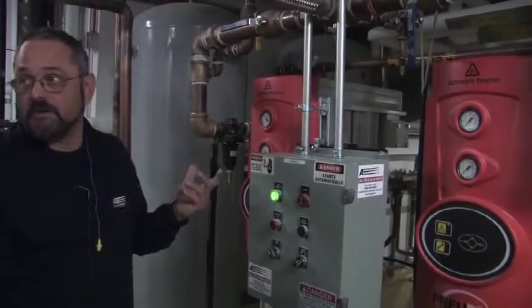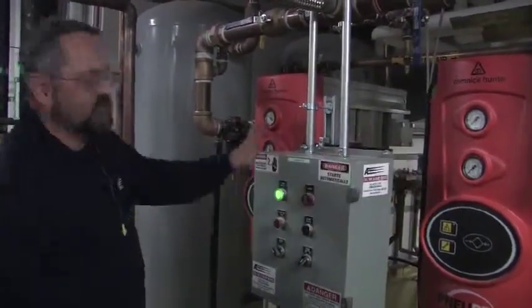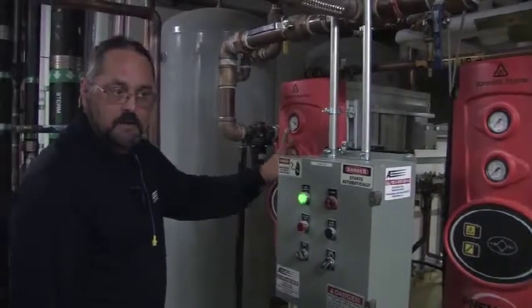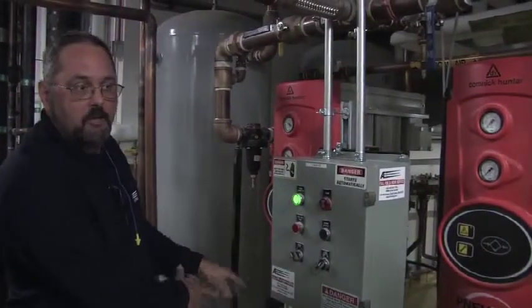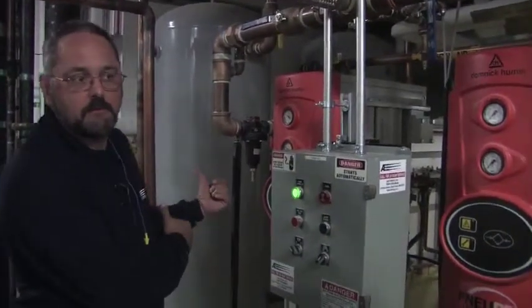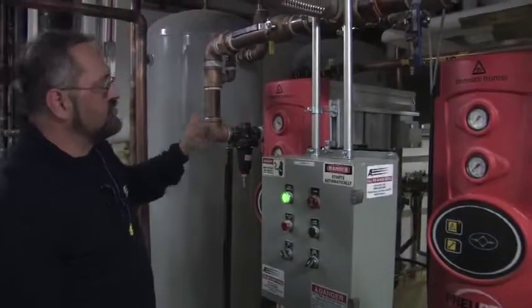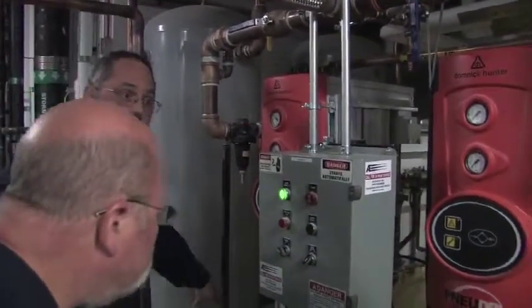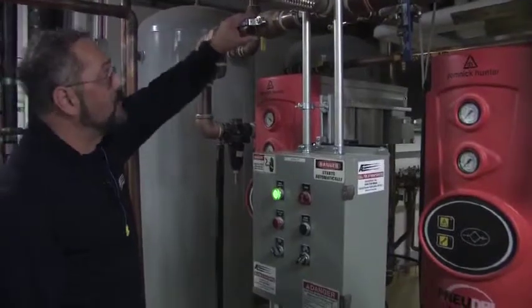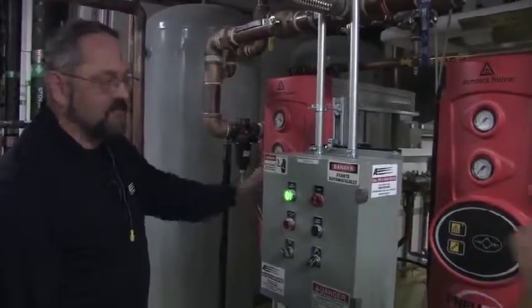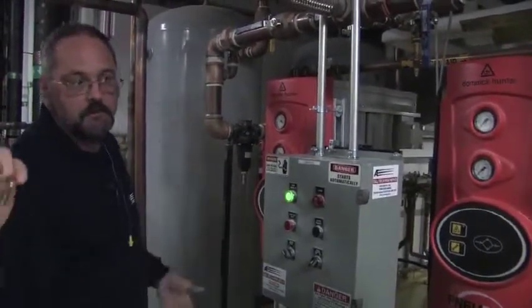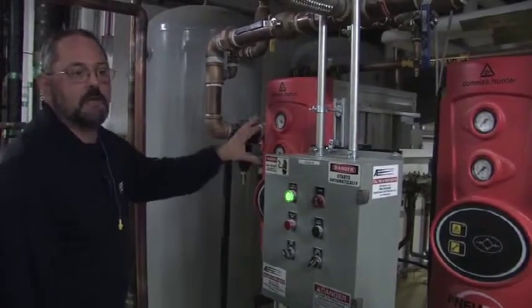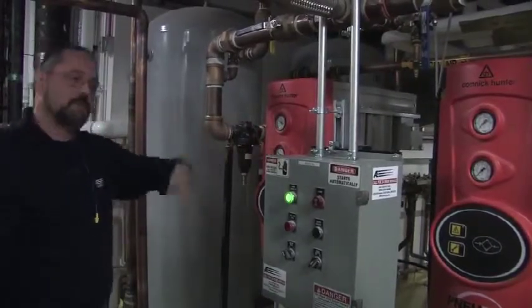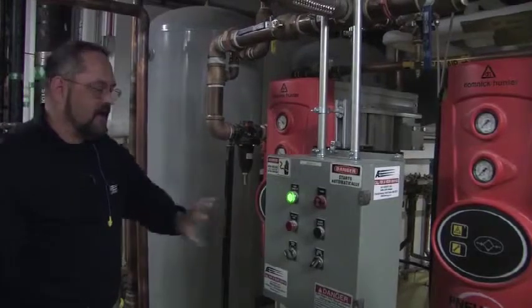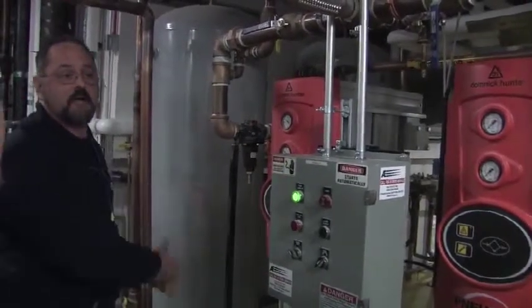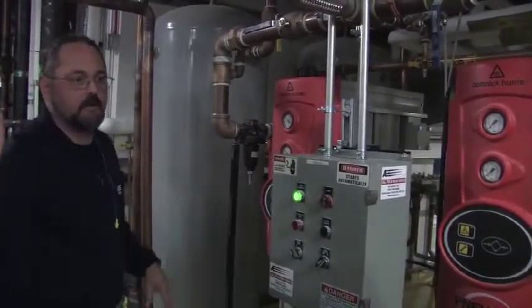Say you did shut one down, or say you had to put this one on because this one failed and was wet. Now you repaired it. Now you want to dry it out before you put it back in standby. So in that case, you would leave the intake valve open. You would shut the outlet valve and leave it powered, and it would just cycle, drying itself out. Okay. And then once you were sure it was dry enough, then you shut the inlet valve, power it back down, or maybe even put that one back online and make sure it works. Okay. And valve out the other one.